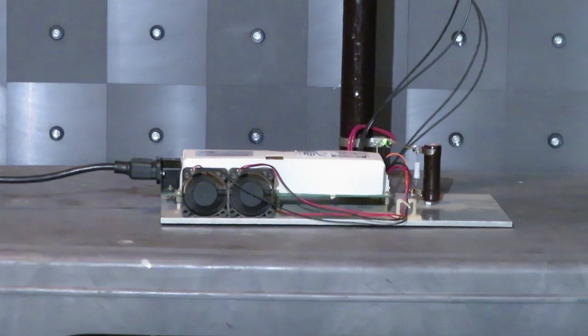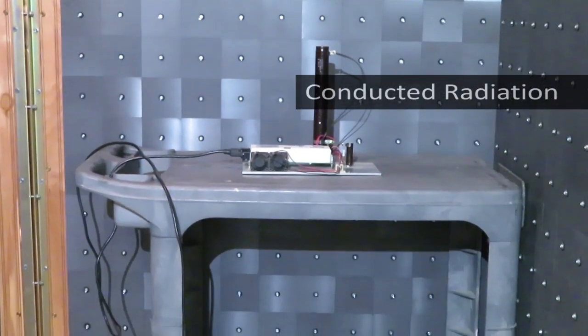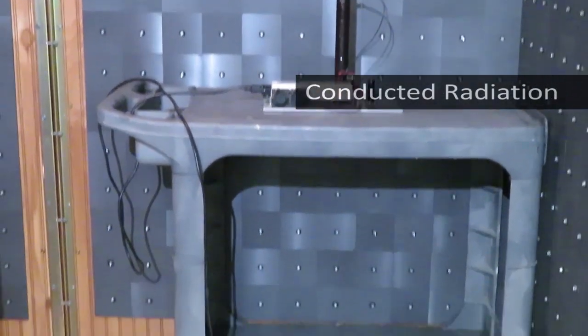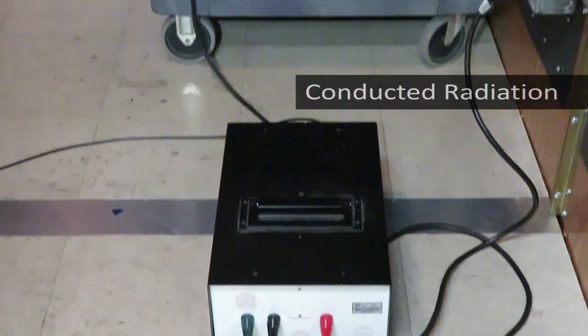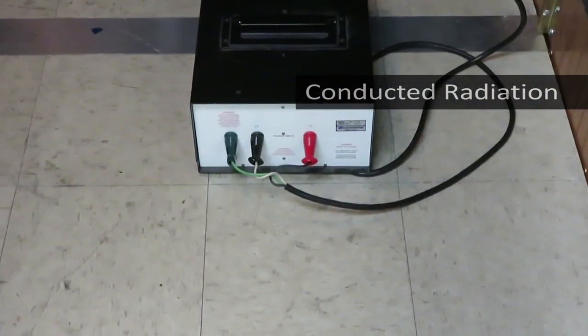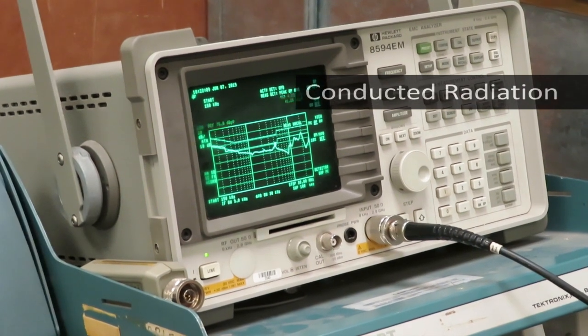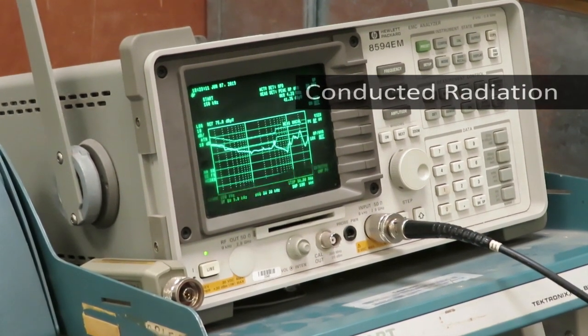We also measure conducted radiation—that is, noise allowed to flow back onto the mains supply line through the device's power cord. For this we use a LISN, or Line Impedance Stabilization Network, to provide a known standard test condition and detect the conducted radiation from the device.